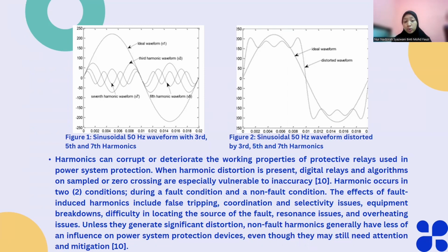Harmonics occur in two conditions in power system protection: during fault conditions and non-fault conditions. The effects of harmonics during a fault include false tripping, coordination and selectivity issues, equipment breakdown, difficulties in locating the source of the fault, resonance issues, and overheating issues. Unless they generate significant distortion, non-fault harmonic generators have less influence on power system protection devices, even though they may still need attention and mitigation.